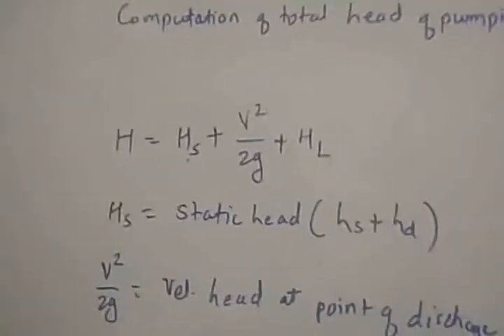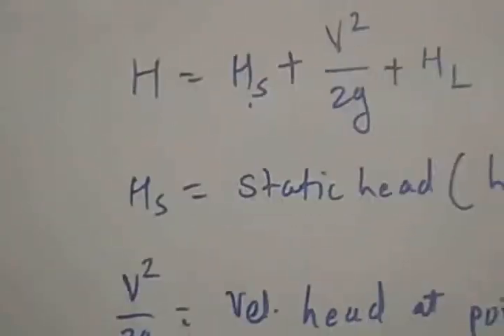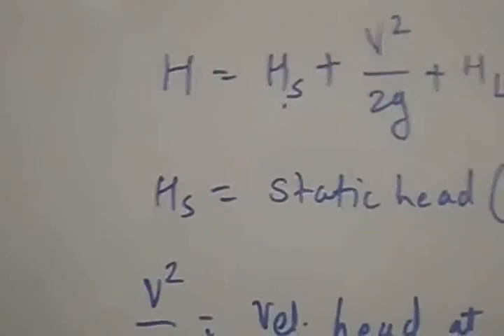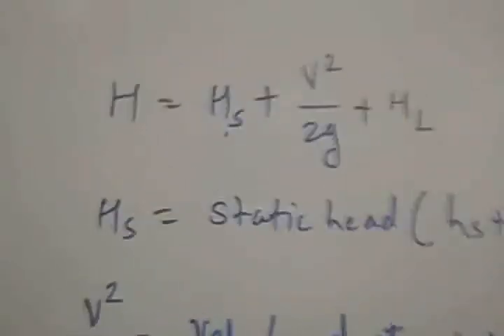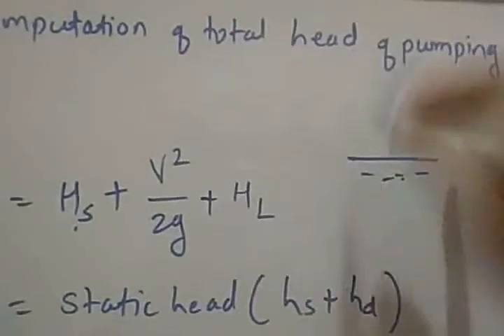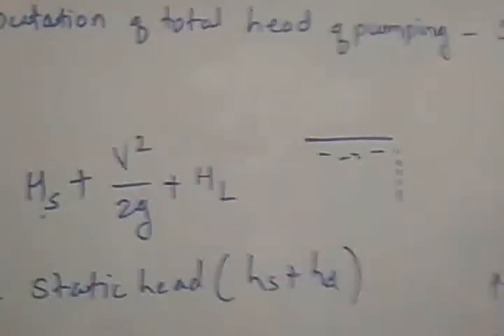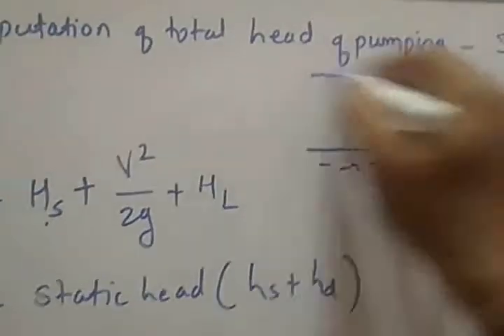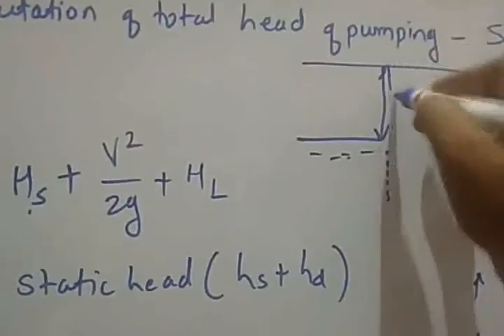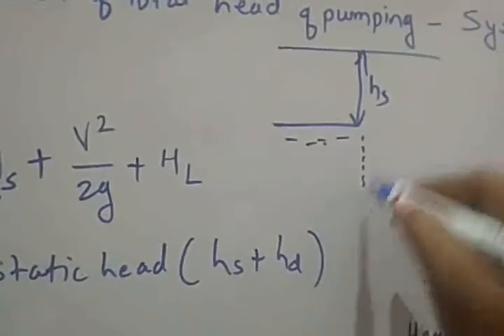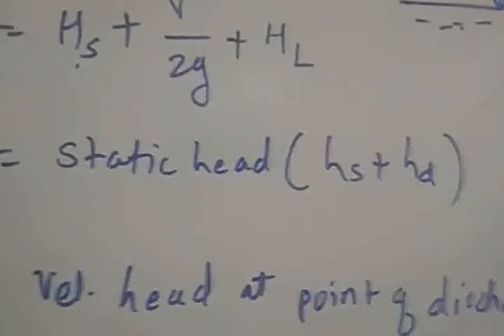Now, if the pump is running and the discharge of the pump is more than its inflow, the level of the liquid in the sump will fall. So if this is the initial level of the sump and discharge is more, this level will go on decreasing. As I am measuring HS from the center of the pump, as the level decreases, HS will go on increasing, so the suction head component of total head will increase.